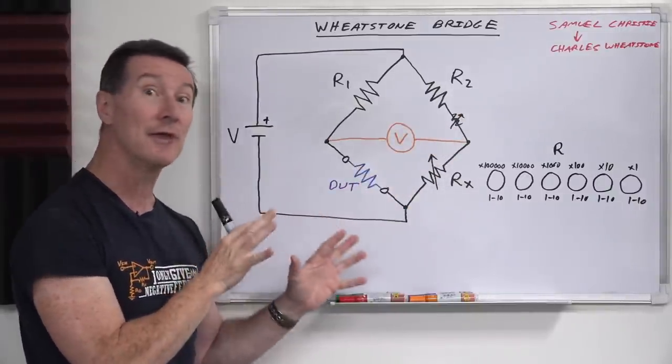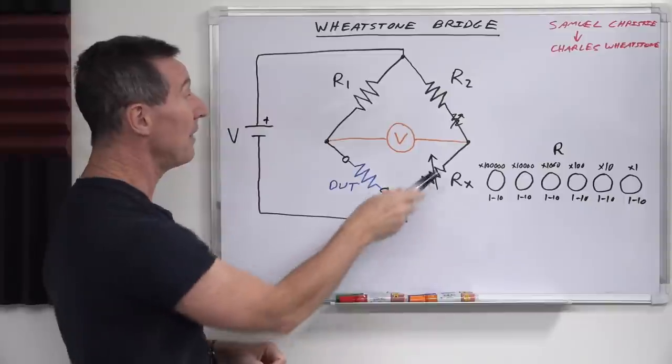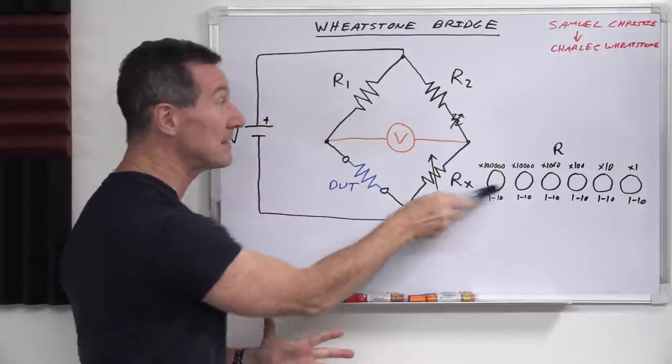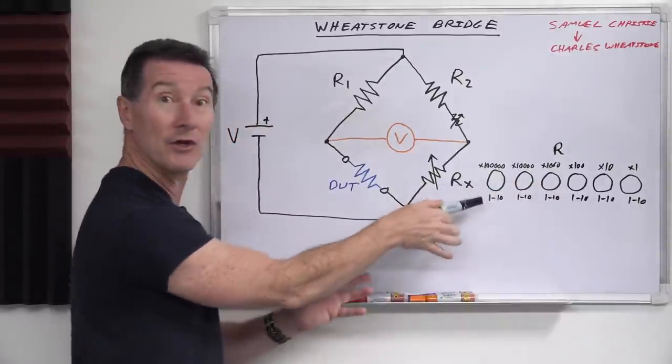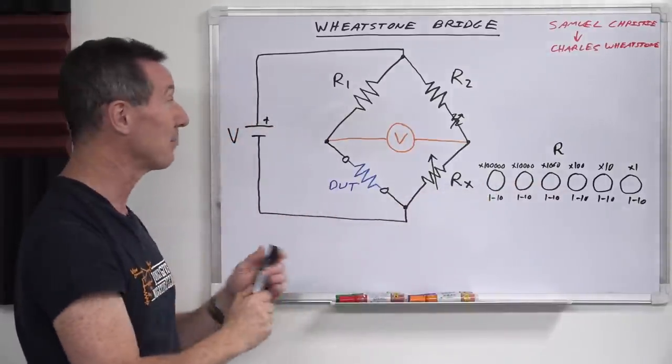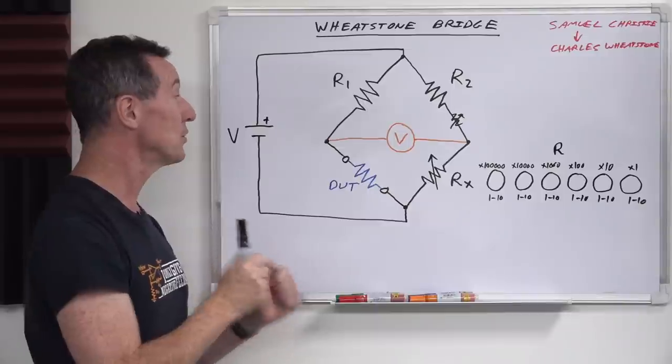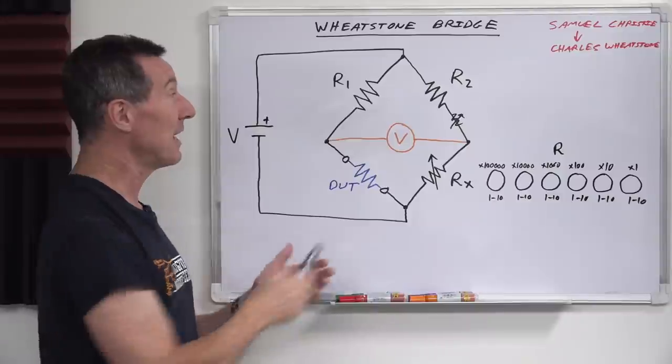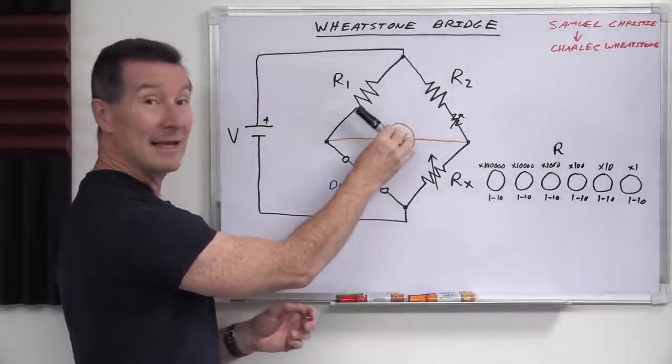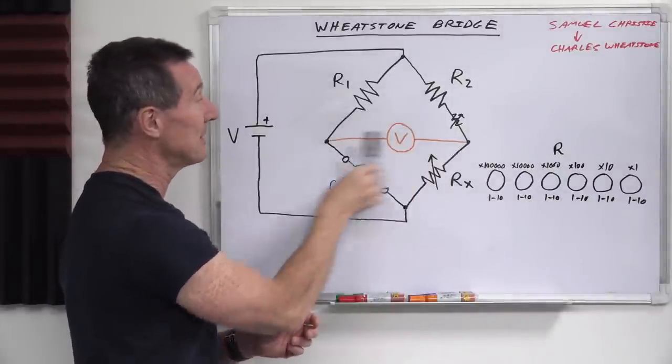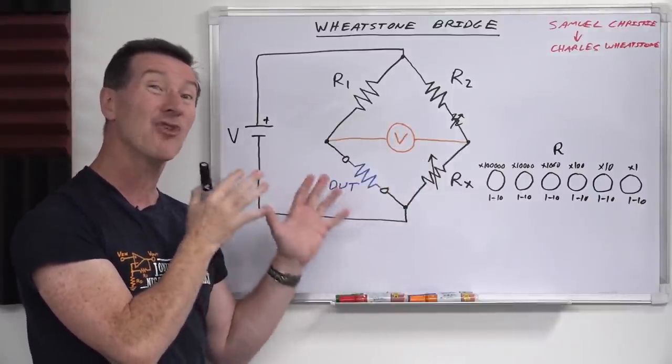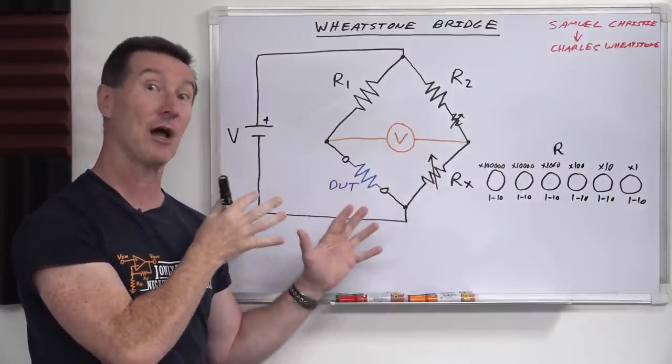And they were the calibration controls that we saw on the front panel there. So once you've actually calibrated this bridge, and you can do that very precisely, then you can actually read off the dials, assuming that these are very precise resistors, but also you can trim these as well. You can calibrate them as accurately as you want to. Then you can just dial off and read your device under test when that meter gets to zero like that. It means there's zero voltage difference between here.